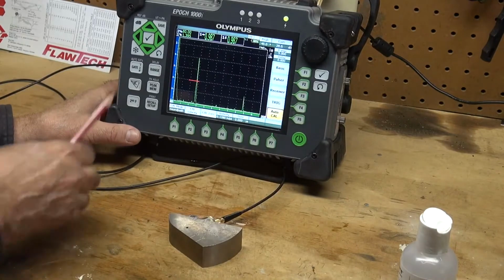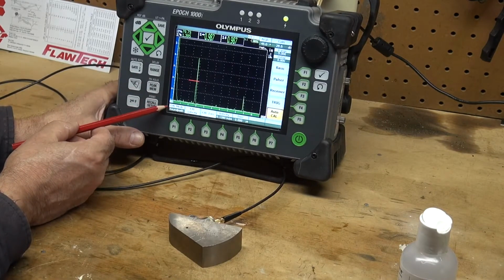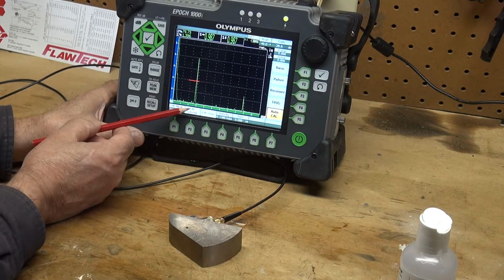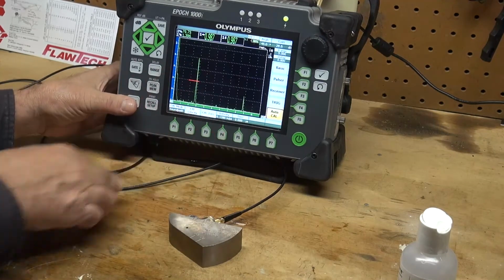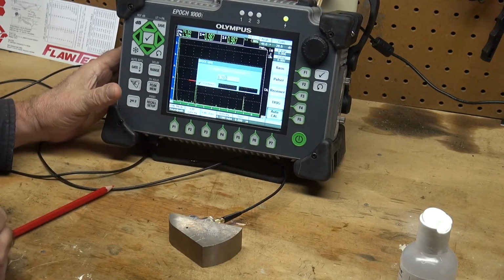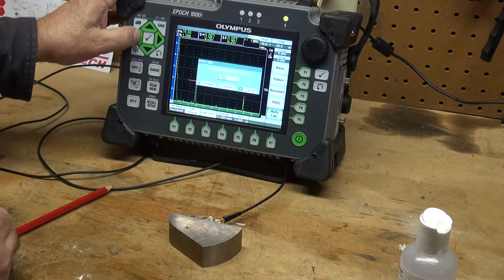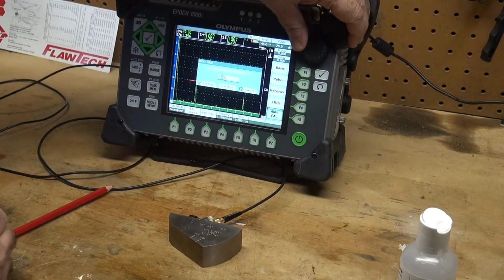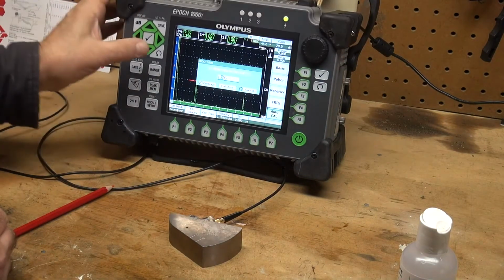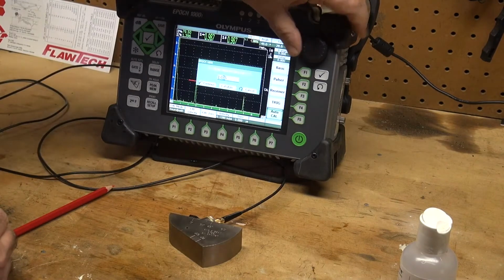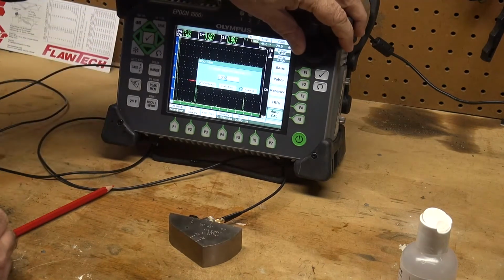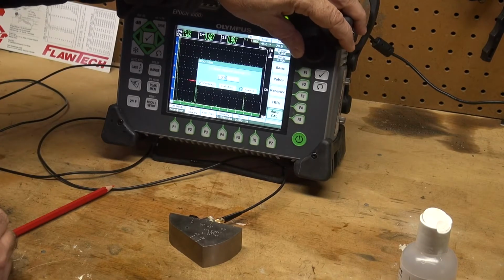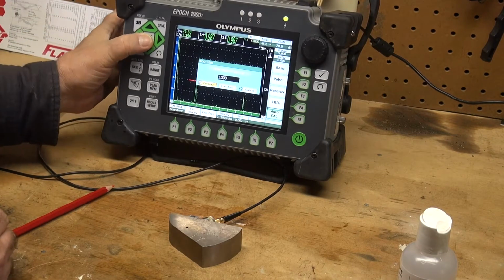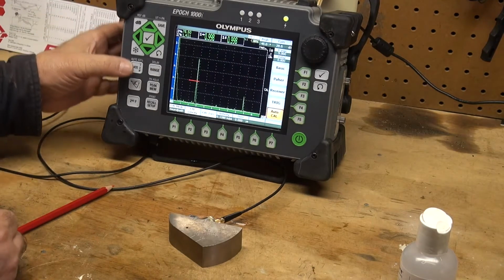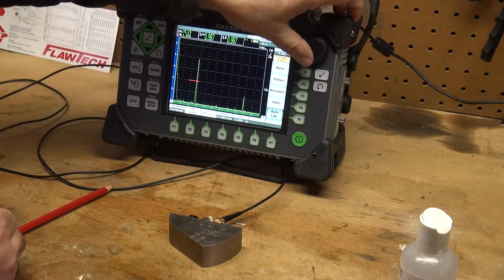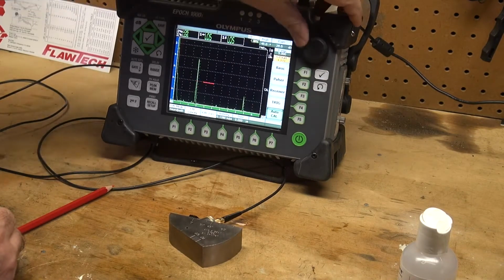auto cal. My cal mode is sound path, and it says cal 0, cal velocity. I'm going to press P3, which is my cal 0, and I'm going to tell the machine what sound path that is. It's a 1 inch sound path. One inch, hit the check button, and then I have to move my gate over to capture my 4 inch radius.